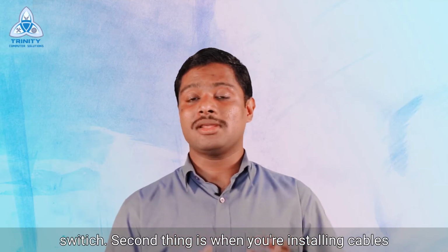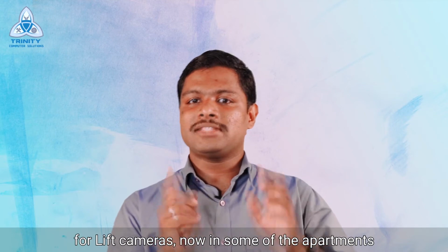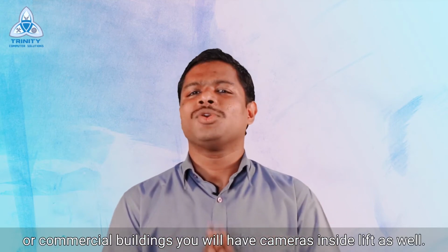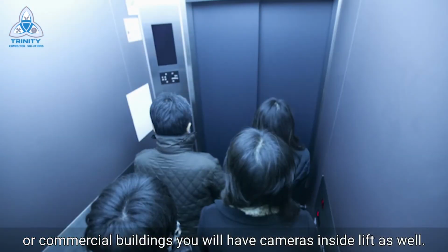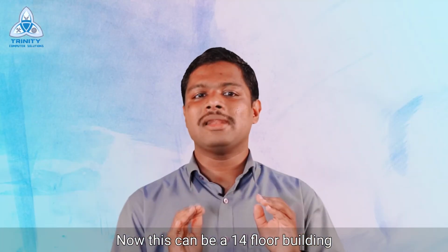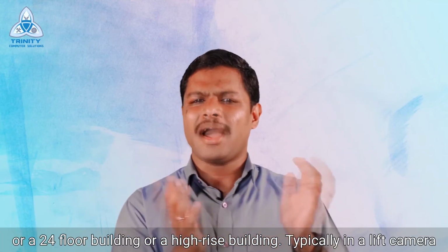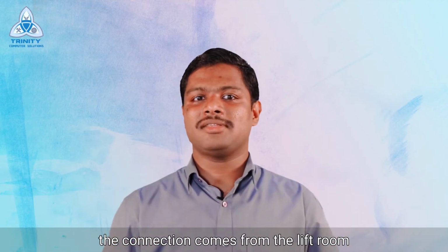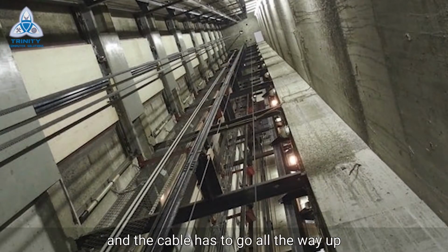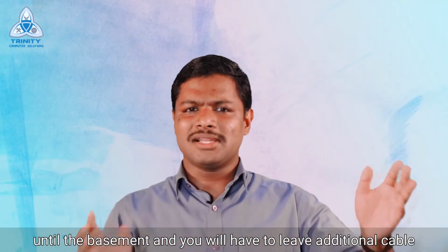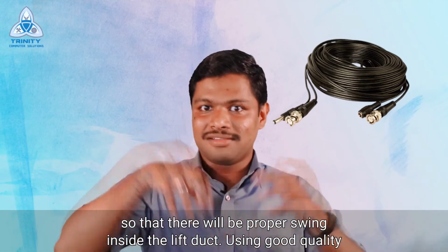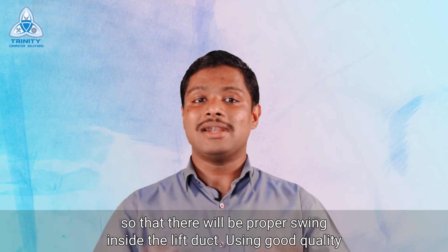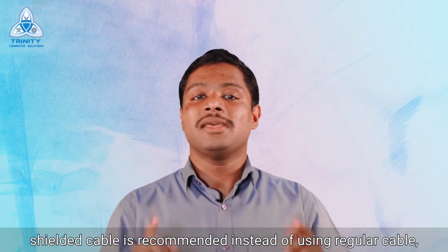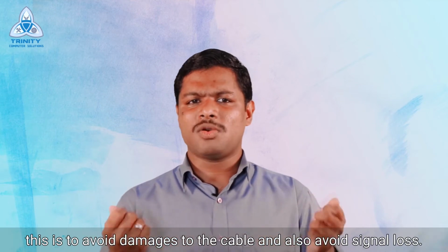Second thing is when you're installing cables for lift cameras. Now in some of the apartments or commercial buildings, you will have cameras inside the lift as well. Now this can be a 14-floor building or a 24-floor building or a high-rise building. Typically in a lift camera, the connection comes from the lift room and the cable has to go all the way up until the basement, and you will have to leave additional cable so that there will be proper swing inside the lift duct. Using good quality shielded cable is recommended instead of using regular cable. This is to avoid damages to the cable and also avoid signal loss.